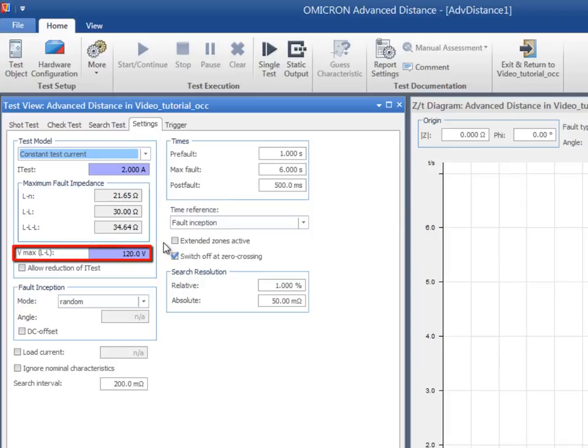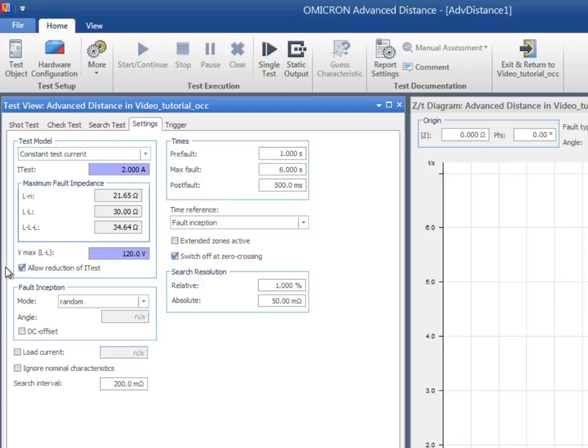either manually reduce the test current or apply the automatic adaptation of test quantities. This poses the risk of preventing the relay from tripping when the test current does not reach the pickup value.